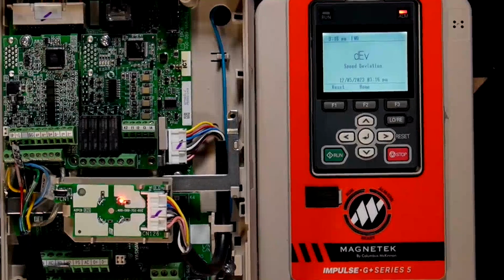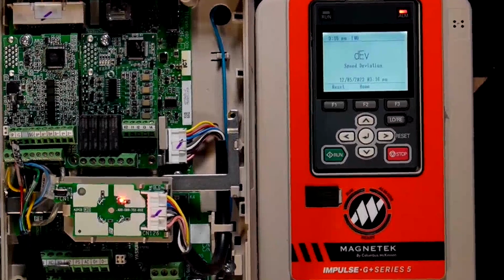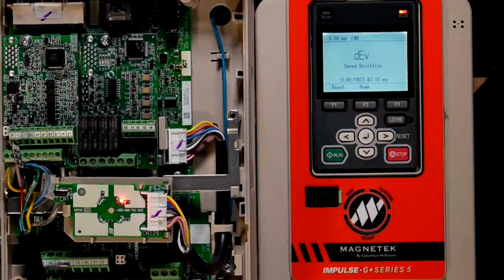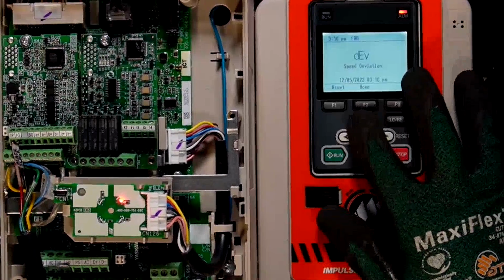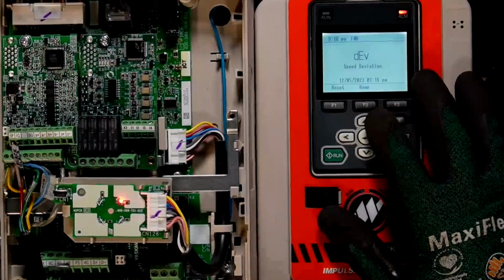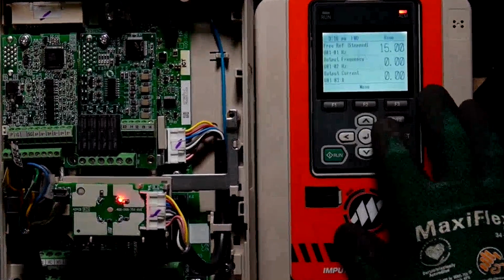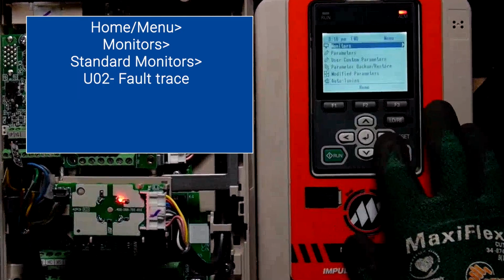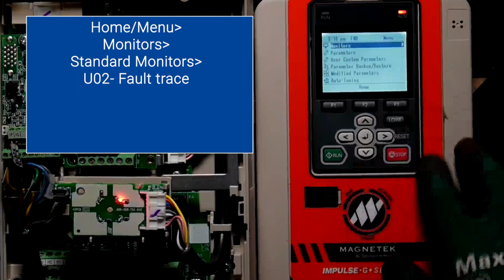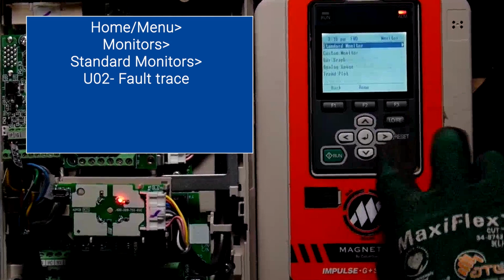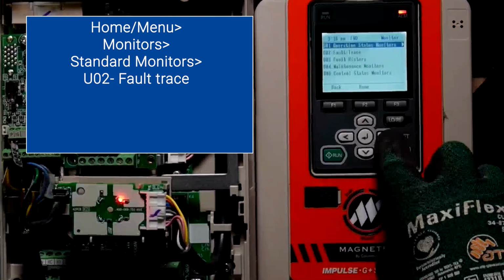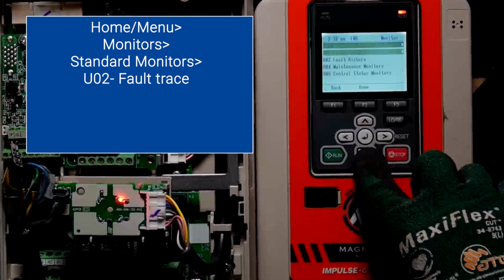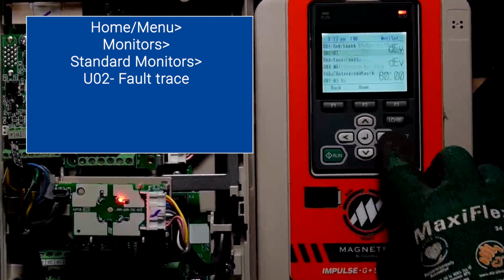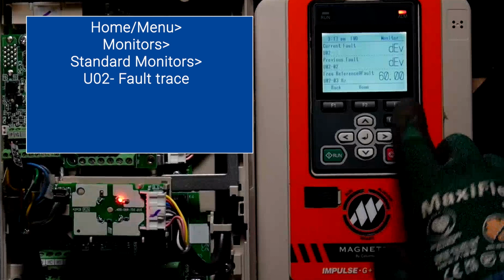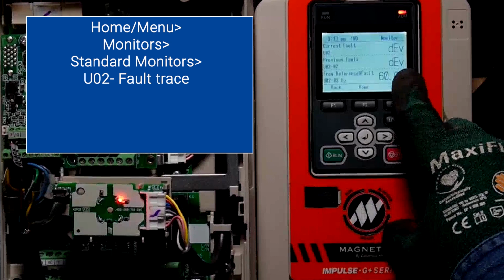Now the question is, how can I determine what caused the speed deviation fault? There's several ways to do it. I'm going to go into the home key, and I'm going to go into the menu, and I'm going to look under the monitor mode, and I'm going to look at the standard monitor, and I'm going to look at the trace data. So right now the drive has a DEV fault.